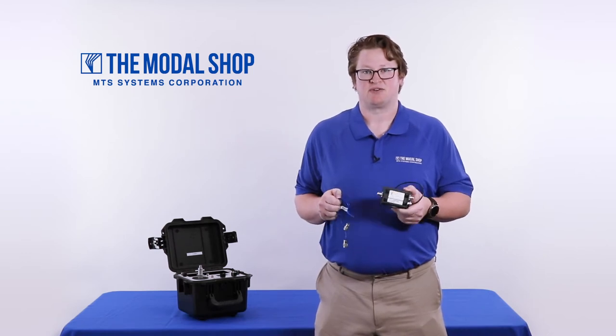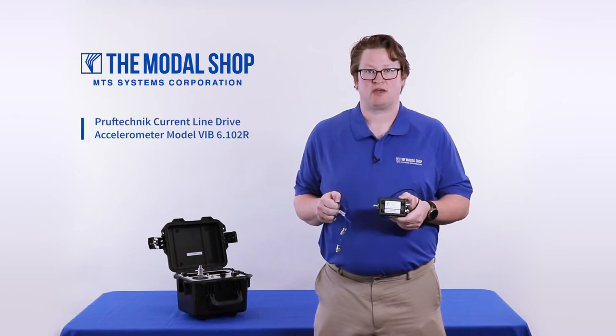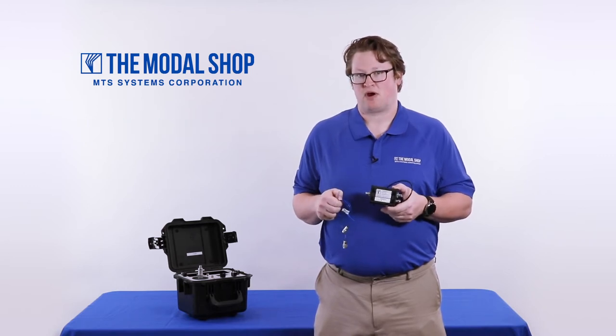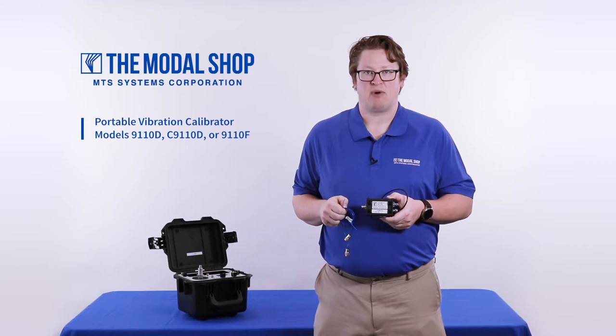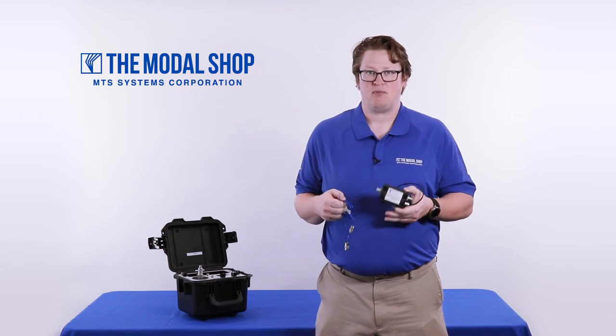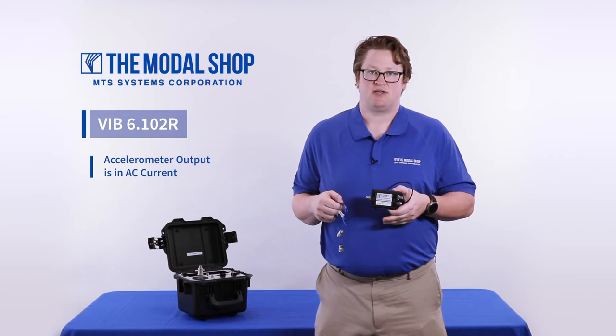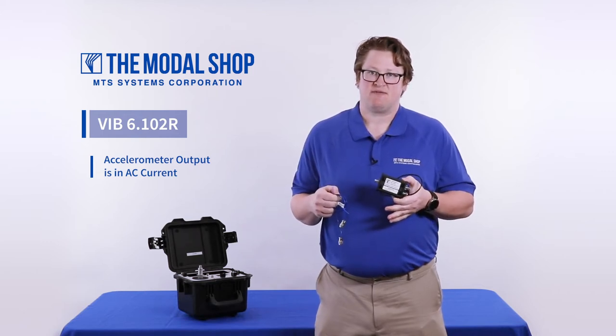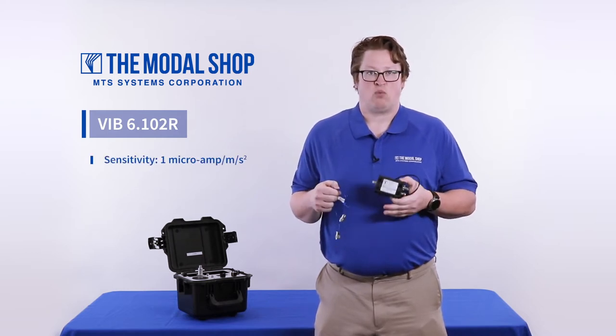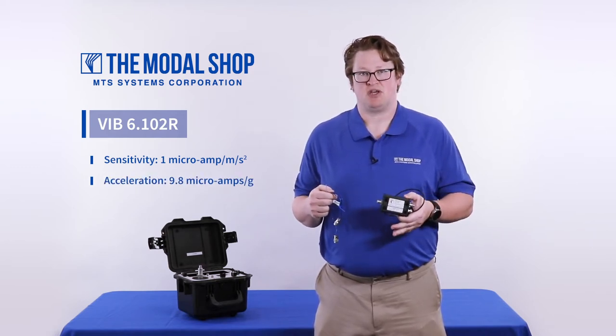Hi, my name is Mike Scott, Industrial Product Manager for the Modal Shop. In today's video I'll be calibrating a PRUFTECHNIK Current Line Drive Accelerometer Model VIB6.102R with our Portable Vibration Calibrator and our brand new Model 9100-PS07-PT signal conditioner. These PRUFTECHNIK accelerometers are unique in the industry because their output is in AC current rather than AC voltage. The VIB6.102R has a sensitivity of 1 microamp per meter per second squared, or 9.8 microamps per g of acceleration.